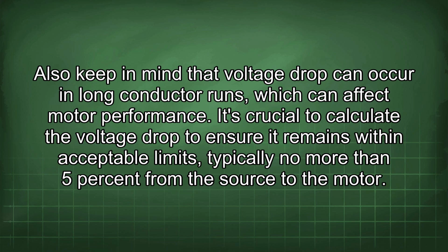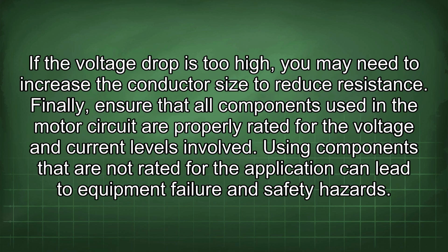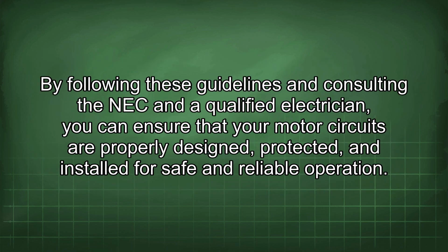Also keep in mind that voltage drop can occur in long conductor runs, which can affect motor performance. It's crucial to calculate the voltage drop to ensure it remains within acceptable limits, typically no more than 5% from the source to the motor. If the voltage drop is too high, you may need to increase the conductor size to reduce resistance. Finally, ensure that all components used in the motor circuit are properly rated for the voltage and current levels involved. Using components that are not rated for the application can lead to equipment failure and safety hazards. By following these guidelines and consulting the NEC and a qualified electrician, you can ensure that your motor circuits are properly designed, protected, and installed for safe and reliable operation.